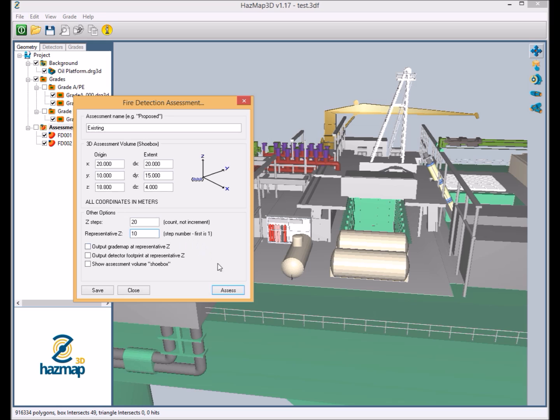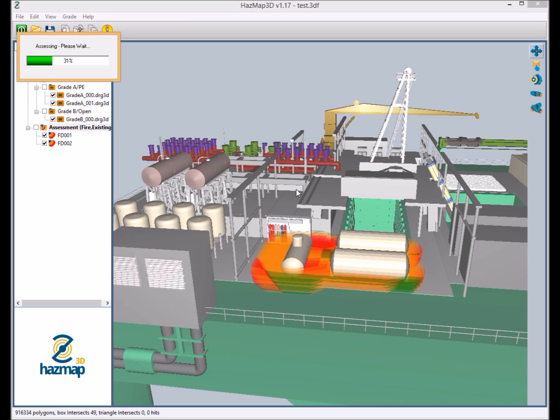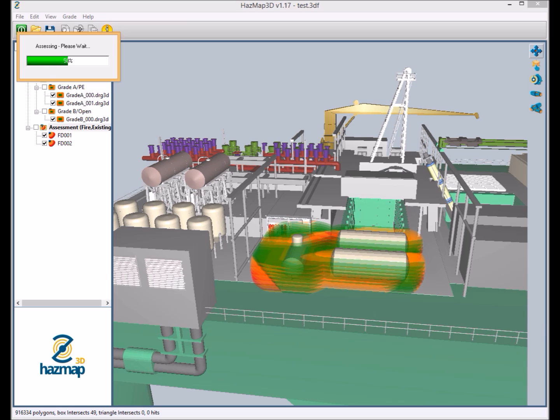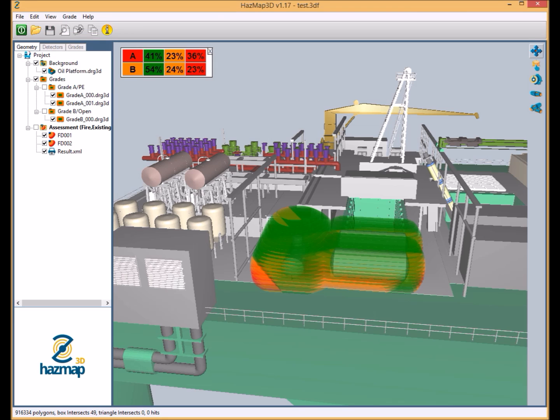So that's still provided in the new assessment as well as the 3D outputs. So we're now in a position to run the assessment. Now what we can see being generated here, what the green would represent is 2 out of n voted coverage for the specific grading rules which have been set before carrying out the project. Obviously if this was a 1 out of n voted system, the results would look entirely different. Similarly, if we had different target fire sizes, it would look different once again.